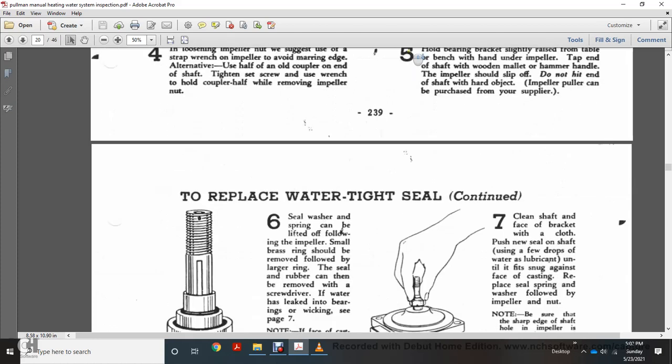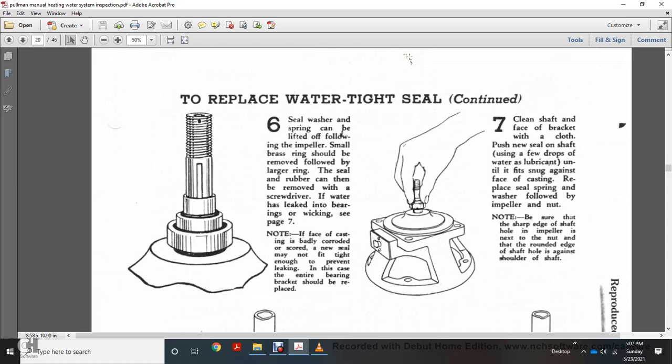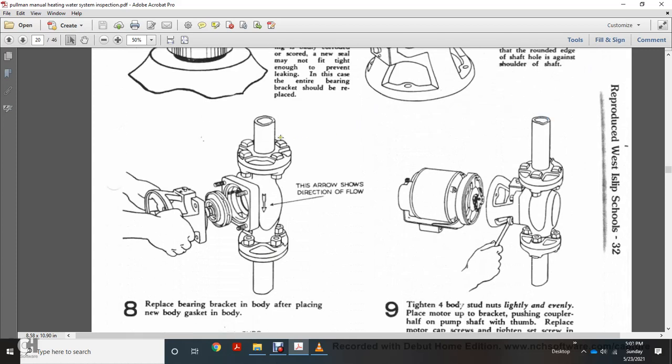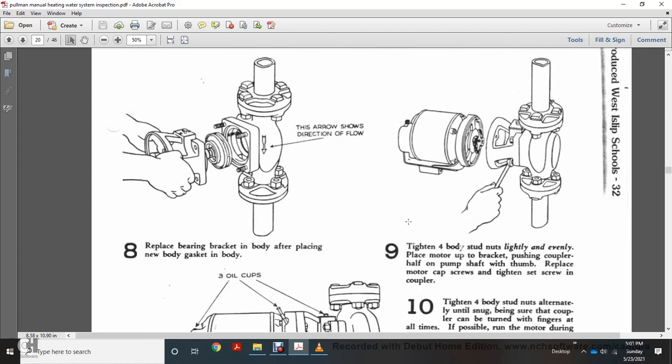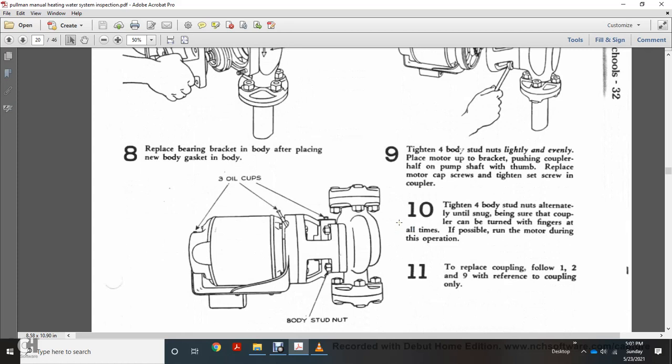Step 6 — to replace watertight seals: the seal washer springs can be lifted, followed by the impeller. Remove the small brass ring; the large ring can then be removed with a screwdriver. If water has leaked into the bearings, see page 7. If the face of the bearing is badly corroded or scored, the new seal may not fit tight enough to prevent leaking, and in this case the entire bearing bracket should be replaced. Step 7 — clean the shaft face bracket, apply the new seal on the face of the shaft, use water as lubricant, and fit against the face of the casting. Place seal spring washer, then the impeller with nut — no sharp edges on the shaft. Hole in the impeller should be next to the nut and around the edge of the shaft against the shoulder. Step 8 — arrow shows the direction of flow. Replace the bearing body and gasket. Step 9 — tighten the four body stud nuts lightly and evenly with the motor bracket, pushing the coupler half onto the pump shaft. Replace the motor cap screws and tighten the coupler. Step 10 — tighten the body nuts alternately until snug. Be sure the coupler can be turned by fingers at all times; if possible, run the motor during this operation.